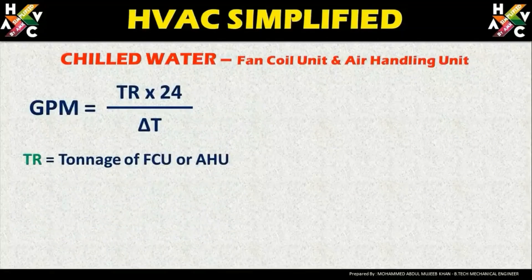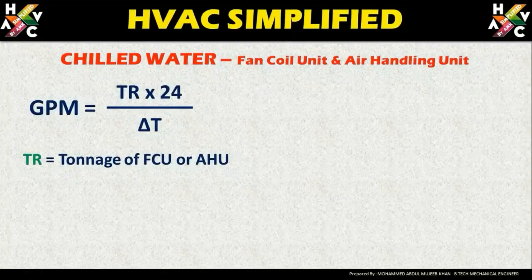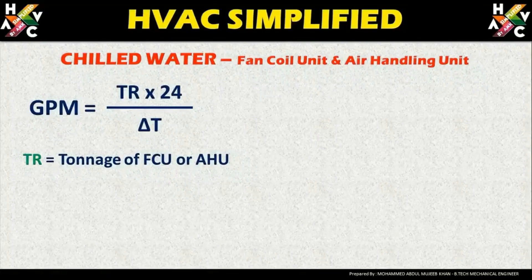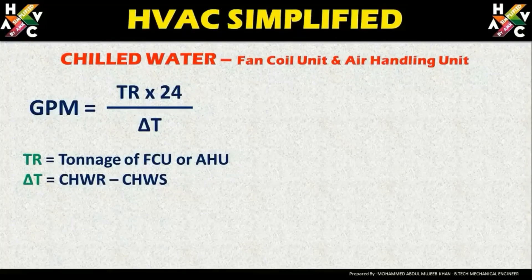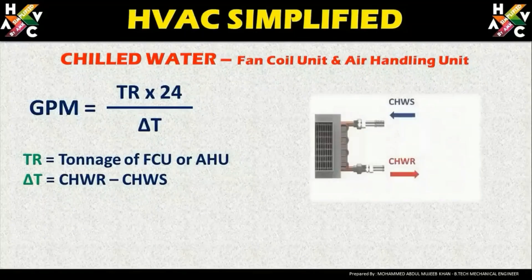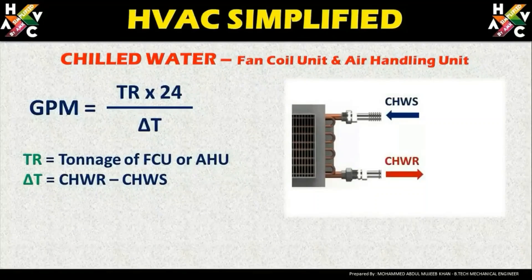TR is the tonnage of the fan coil unit or the air handling unit, which you get from the load calculation. This is the tonnage required for a particular fan coil unit or air handling unit. Delta T is equal to chilled water return temperature minus chilled water supply temperature.